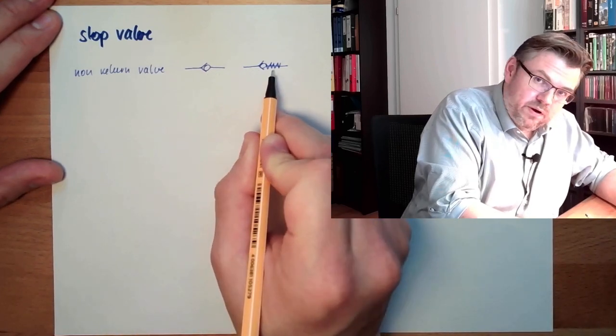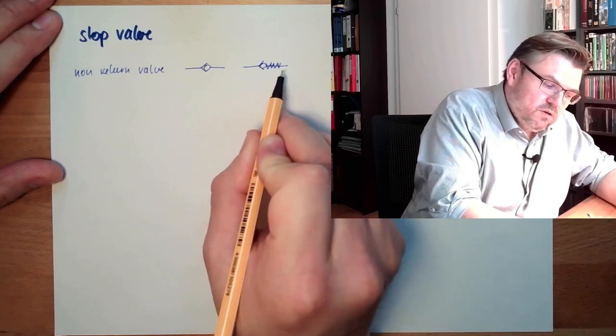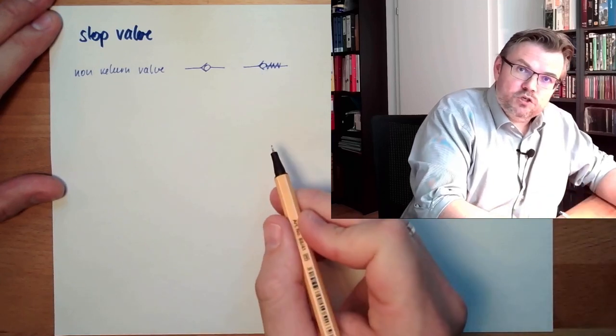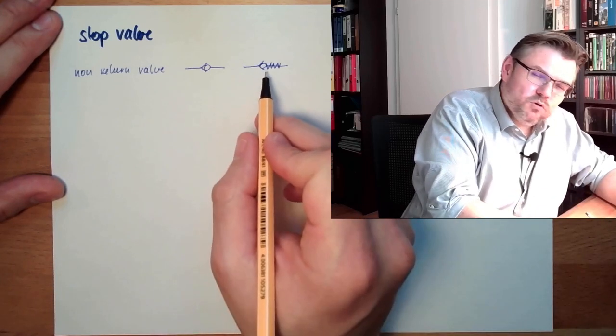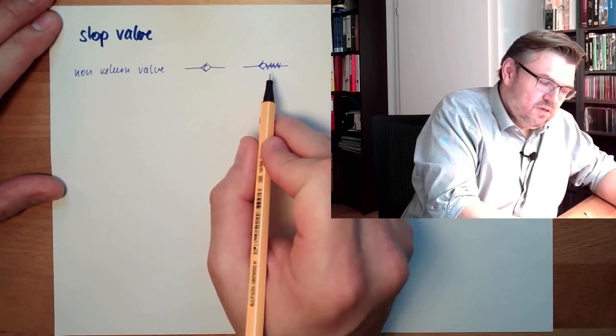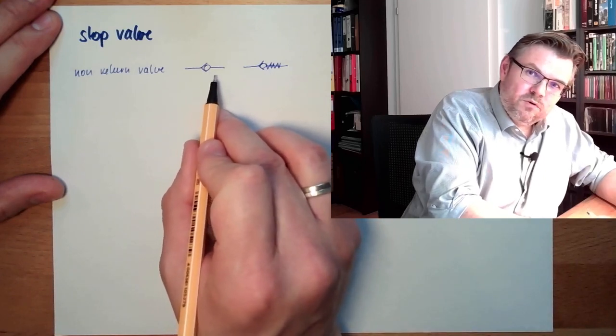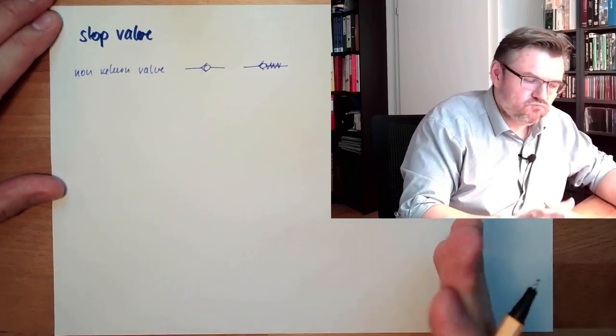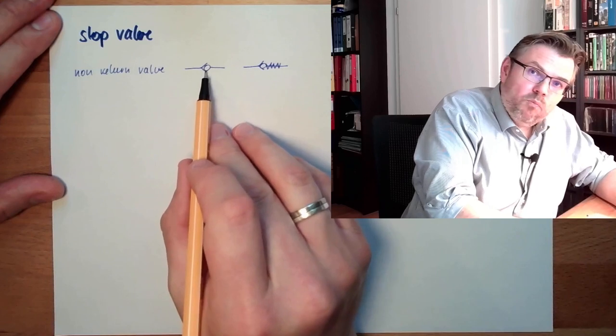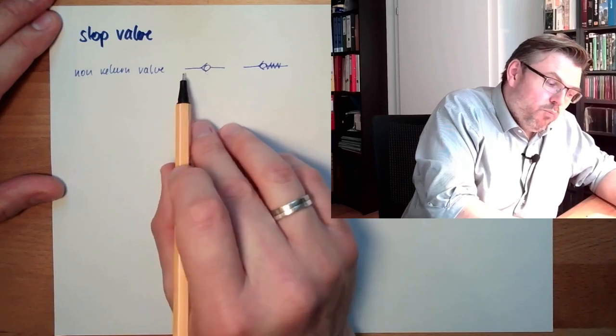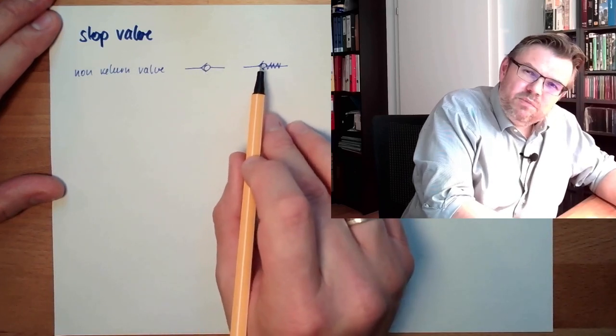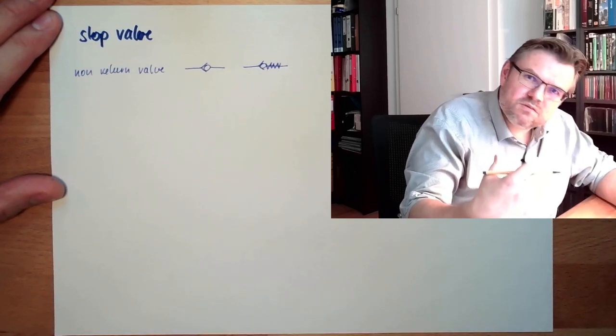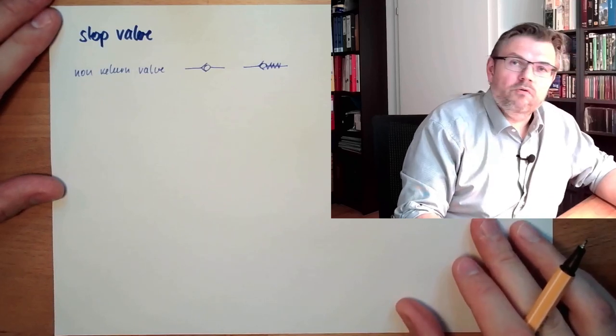Without spring. With spring — if pressure is on both sides equal, the spring-loaded one has a defined position and is also working regardless of gravity. The non-spring version is sensitive to gravity and has an undefined position if both pressures are equal. This will open at low pressure differences, whereas the spring-loaded one needs a little bit higher pressure differences because you also have to push the spring.